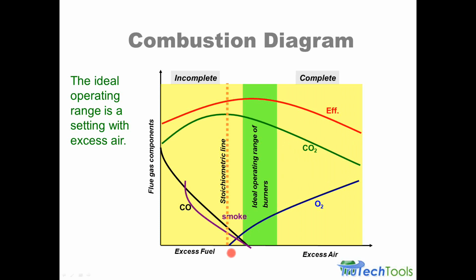The thing to be careful of, with some of the older technologies, the wet chemical technologies, they call them shaker bottles or Fyrite, or the modified ORSAT method, you can notice that the CO2 line is not unique. For any concentration of CO2, there could be two values, one over here and one over here for the same concentration of CO2. So without some additional information, the CO2 reading by itself doesn't provide enough information as to what line you are on, what side you are on, excess fuel or excess air. Carbon monoxide can help with that. So a meter that has combined carbon monoxide and CO2 sensors is viable for determining a unique point in the combustion curve, to tell you which side you're operating on.